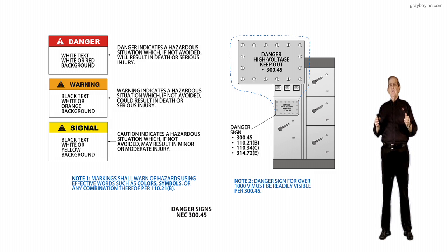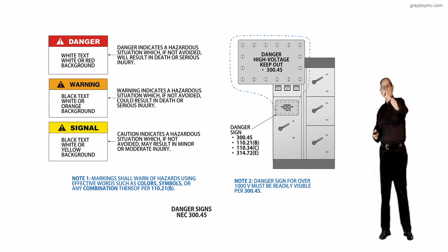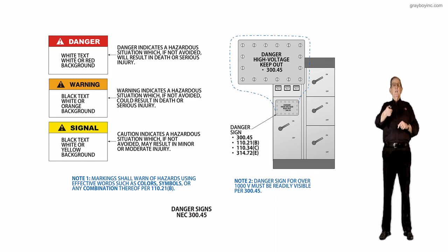For example, you could have a cover that had danger on it, and usually when you open the cover up, right there, you're in the energized components immediately. But if you read Z535.4, I could open the cover and I could have an orange sign on it if you had to remove a second cover that would have the immediate danger sign listed there.